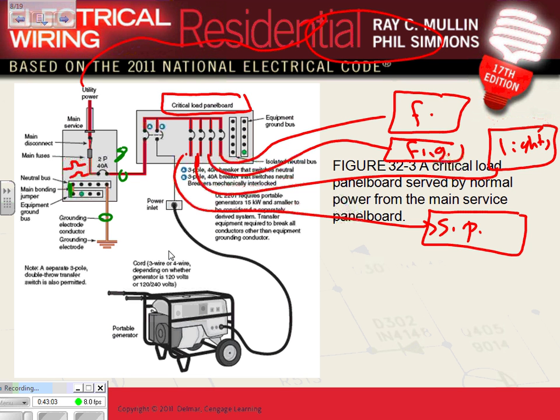Any question about this? Two mechanical interlock. Okay, so I have my 40 amp. I have my 40 amp over here too. And then all these could be 20 amps each, feeding different loads. So here's what happened, guys. Normally, you're running with 40 amps and all your equipment are running from the grid.